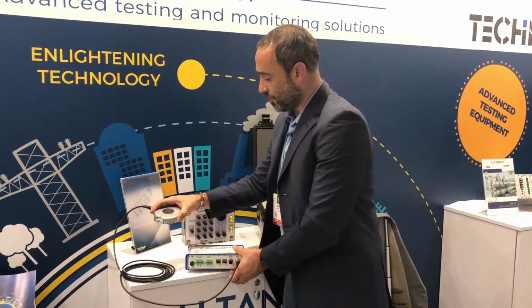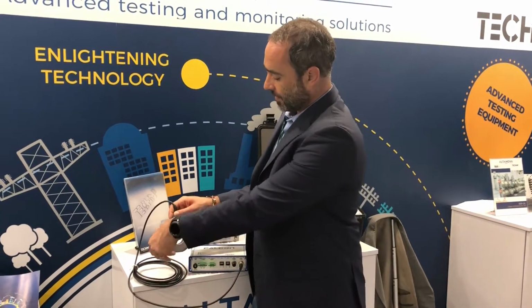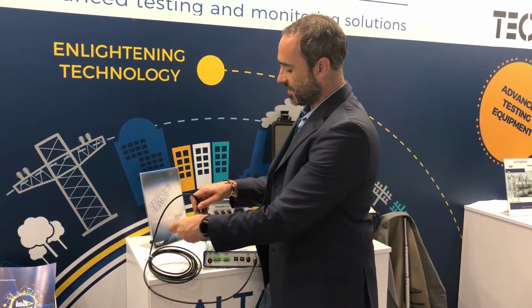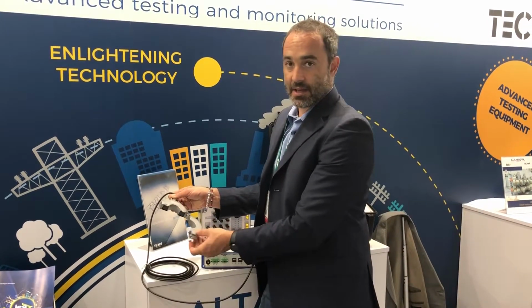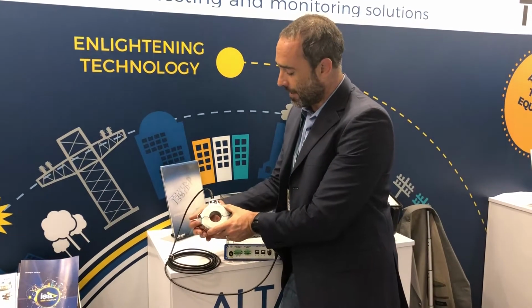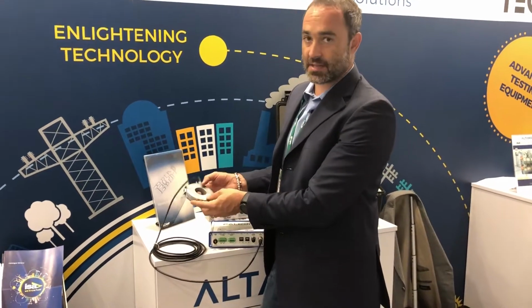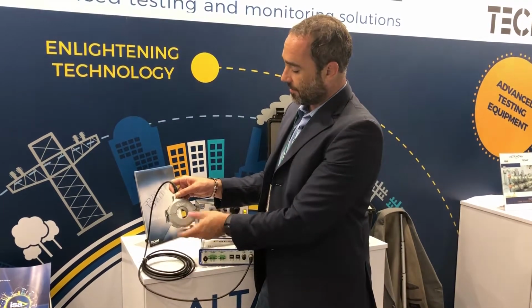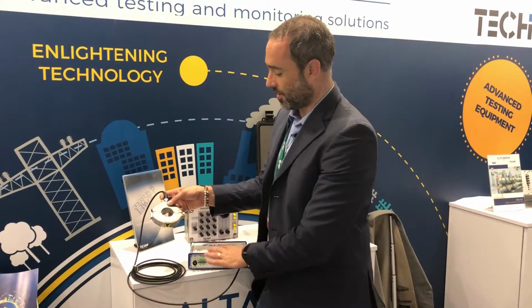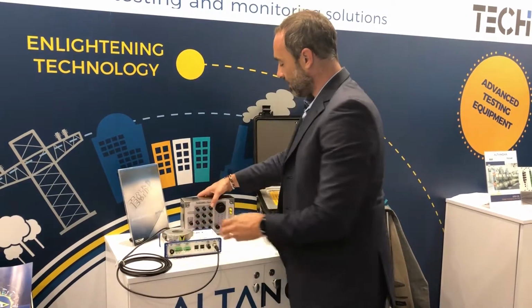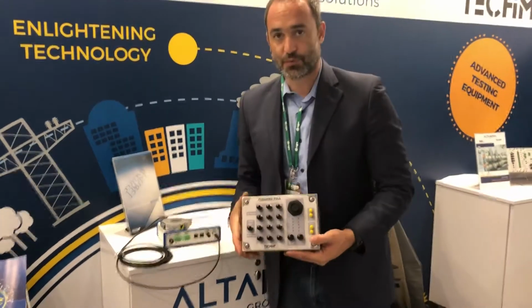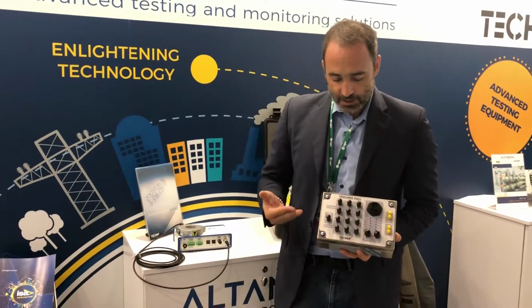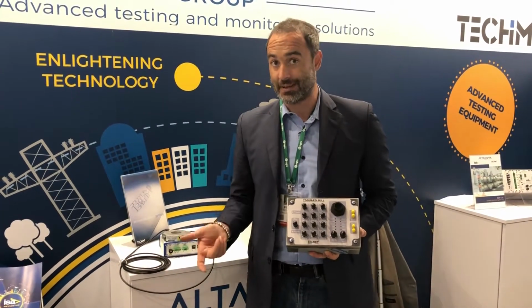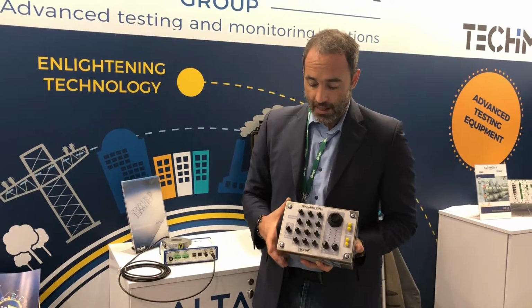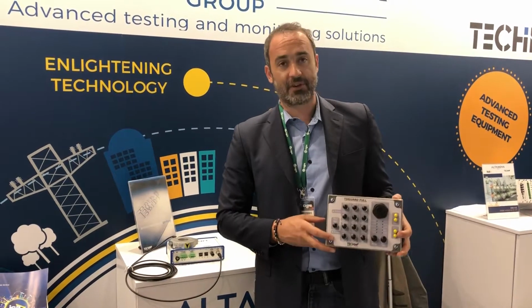Coming back to the new Techimp sensor, this is the new Techimp HFCT sensor with the highest sensitivity until now, up to 25 millivolts per milliamp, and also a fantastic frequency characteristic. So this is something you will be buying hopefully in the future. The device which I want to show you is used for transformer monitoring. If you want to do not just the monitoring of the PD on the transformer, but also the monitoring of tan delta, then you will use a device like this.